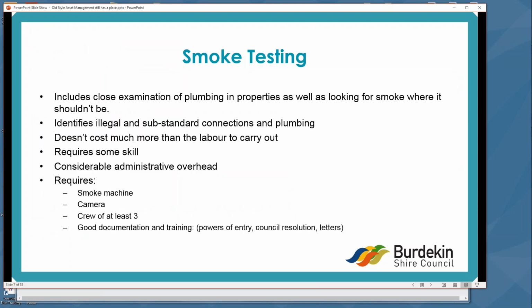So smoke testing, for those who aren't all that familiar with it, includes a close examination of the plumbings on the property as well as looking for where the smoke shouldn't be coming out. So it helps identify illegal and substandard connections and plumbings on the properties. And it really doesn't cost much more than the labour to carry out, although it does require some skill, and that's where we have some problems.